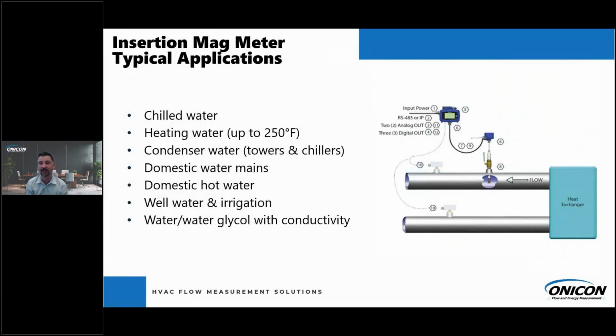So what applications is this technology good for? We originally designed this for open loop cooling towers. Back in the 80s, all we had was the turbine flow meter, which was great for chilled water and hot water, but not great for open loop systems. So we designed this insertion mag meter to handle those open loop systems.